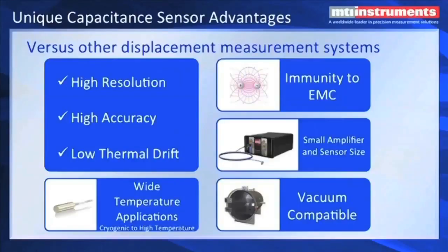Capacitance sensor advantages versus other displacement measurement systems. Well, obviously contact probes are something that a lot of people want to avoid because of the loading and scratching of high precision parts that you're trying to measure. Capacitance has high resolution, high accuracy, and low thermal drift. These are probably the three main features of capacitance gauging.